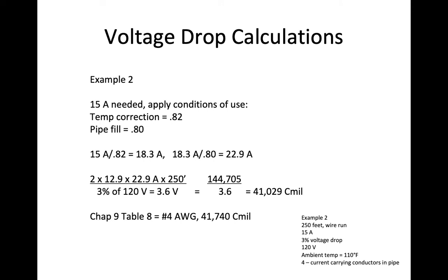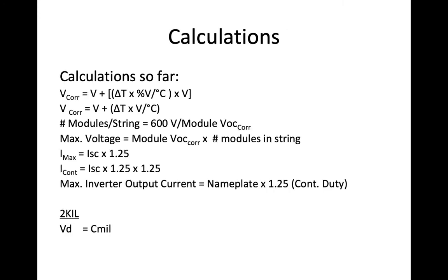Here it is all laid out for you. These are all the equations we've used so far in this class. Here's the temperature correction calculations, temperature coefficient calculations for a string. I'm going to divide the answer from this to get my number of modules in a string. I'm going to take module maximum voltage in a string. I'm going to take module Voc corrected times the number of modules in a string to get Vmax.